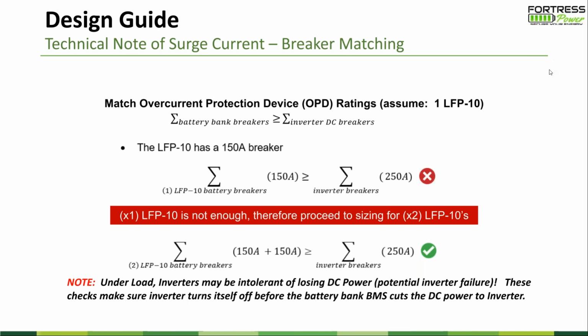So if you want to go with LFP-10, it only has a 150 amp circuit breaker, and you want to match it to the Schneider XW, which has a 250 amp circuit breaker. It doesn't match. If the inverter puts out too much current, it's going to trip the DC breaker on the battery first. The system is going to shut down. Schneider doesn't work without DC power input. That's how the system works.